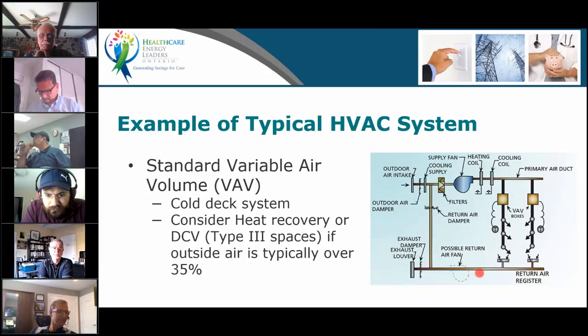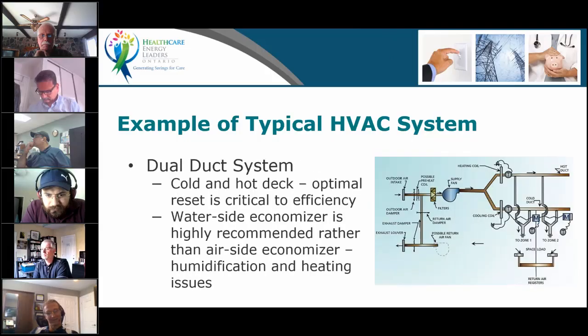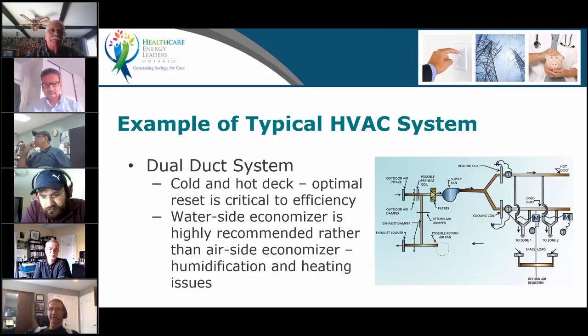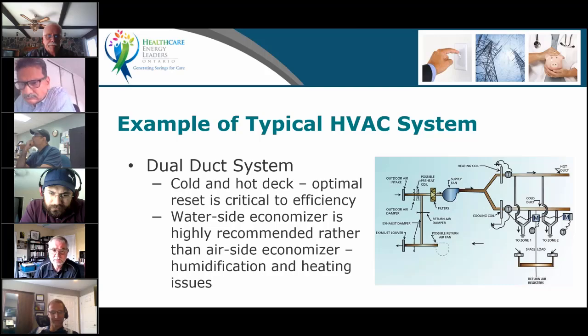And there are a few other examples here that I'll go through quickly. If you have a dual duct system, a lot of older, larger buildings had those. I've done a few audits and recommissioning in the Gaspé Peninsula hospitals, and they had dual duct systems. They are very complex to optimize in their controls because you have one fresh air intake. With a single fan dual duct, it will supply the same air to a hot deck, which supplies your heating, and a cold deck. How do you optimize the amount of fresh air you get in here? It is very difficult. If you want to do free cooling, you will dump a lot of cold air in your hot deck. It will cost you a fortune.